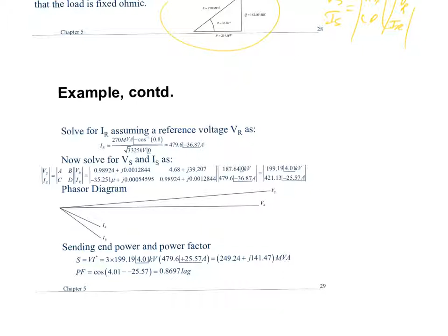I like to draw the phasor diagram a lot, because that tells me something. If you notice the magnitude of VS is greater than the magnitude of VR, that means reactive power is flowing from the sending end to the receiving end. It also tells me there's a phase shift between those two, which tells me VS is sending real power to VR. So just by looking at this phasor diagram, I can tell you the magnitude of VS is greater than the magnitude of VR.